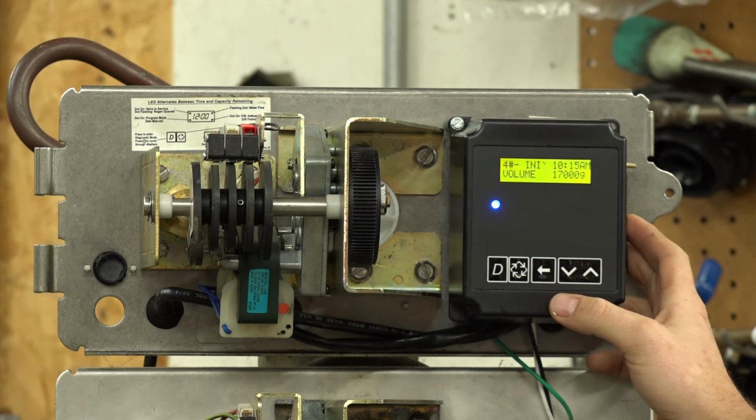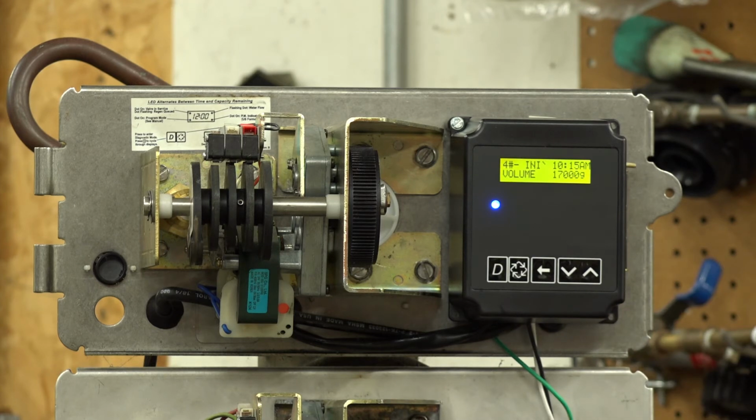Once you're done with that, it says programming, please wait, and that's when it will save all your programming that you just did. If you do not go through that last step, after about 1.5 to 2 minutes it will go back to standard display and it will not save. So you need to make sure that you see that programming, please wait. That is also when it will synchronize your pistons on a twin, triple, or quad system. Up until that point, it won't shift things around because it's waiting for the programming to finish.